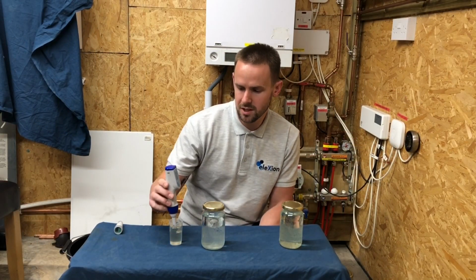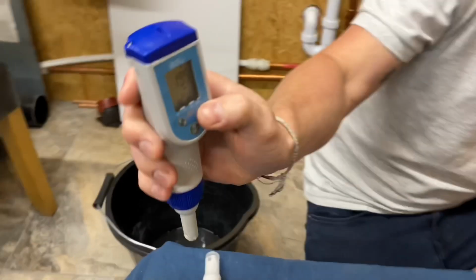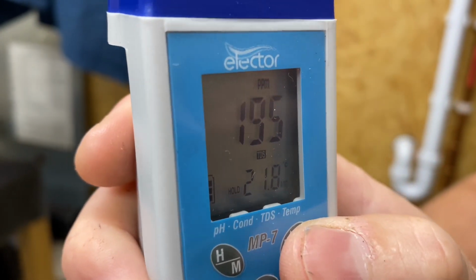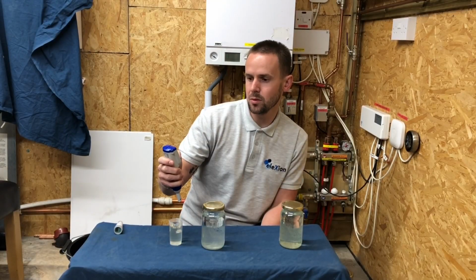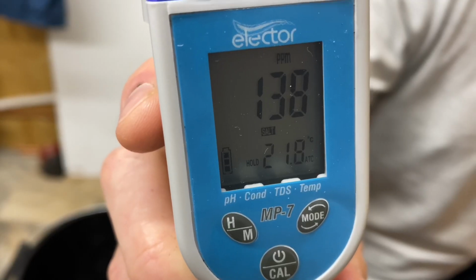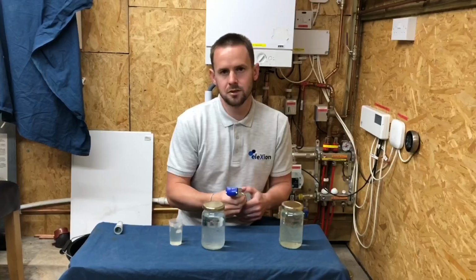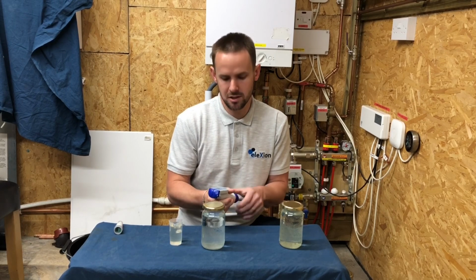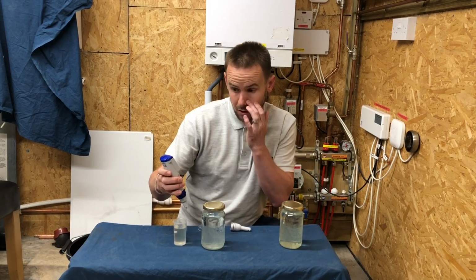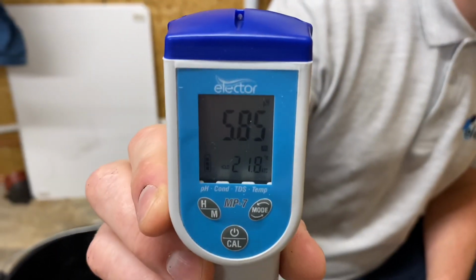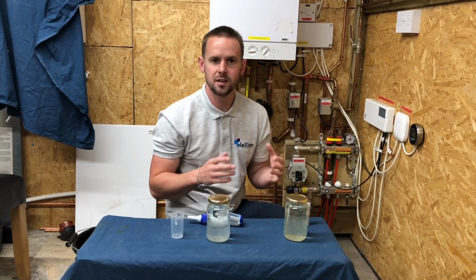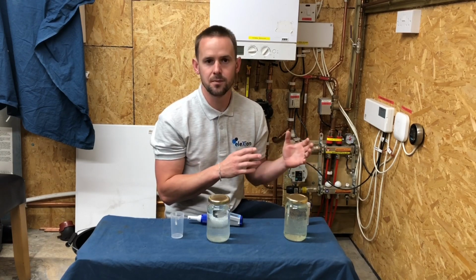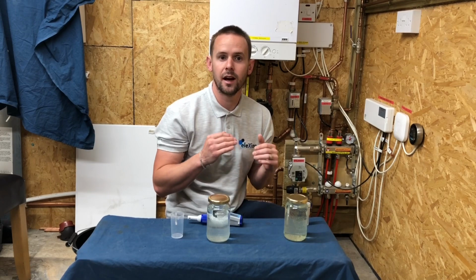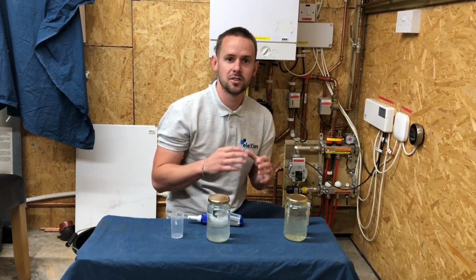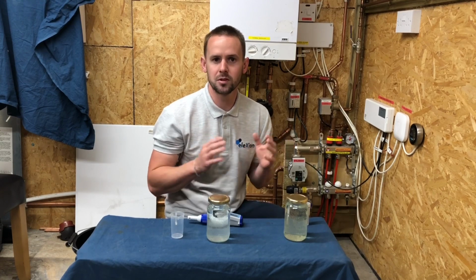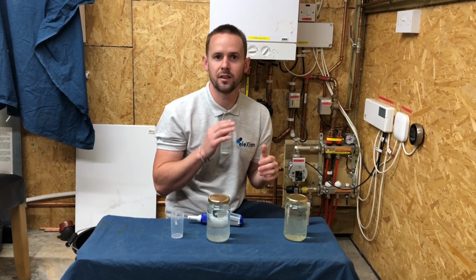Just going to check what the TDS is. The TDS is 195, and then I'm going to check what the salts are. 138 parts per million. Now we're going to change the probes and check what the pH was. We've got a very low pH here of 5.85. From those test results, we can see that there clearly was some residue cleaner left in the system. Our pH had decreased and our conductivity had increased. So basically that's not what we want. We want a conductivity of less than 100 and our pH around 8.5.